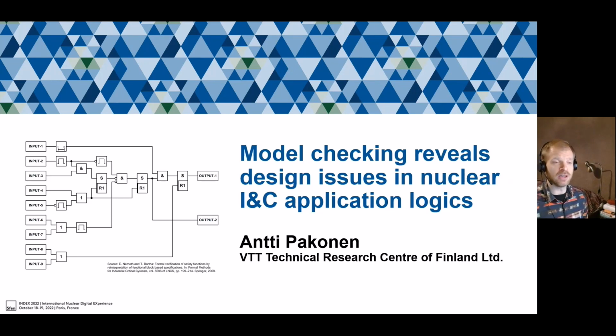Function block diagrams, like the one you see here, are a common specification or programming language for I&C logics. But the problem is that given sufficient complexity, you cannot rely just on testing to prove that the design is 100% correct.